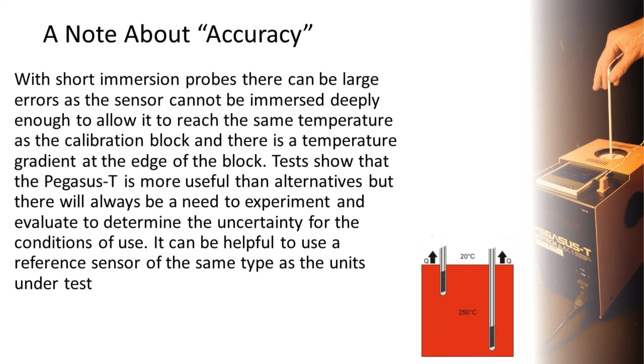A note about accuracy. With short immersion probes, there can be large errors as the sensor cannot be immersed deeply enough to allow it to reach the same temperature as the calibration block. There is also a temperature gradient at the edge of the block. Tests show that the Pegasus T is more useful than alternatives, but there will always be a need to experiment and evaluate to determine the uncertainty for the conditions of use. It can be helpful to use a reference sensor of the same type as the units under test.